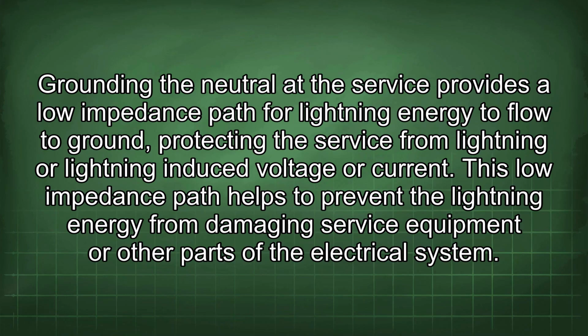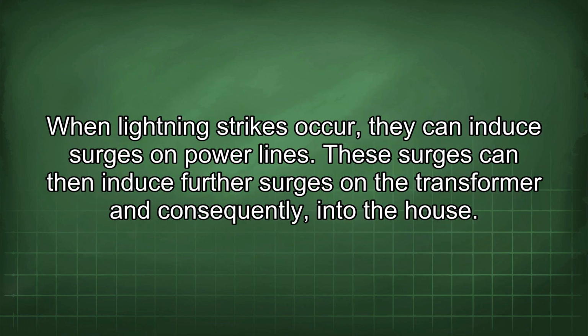Grounding the neutral at the service provides a low impedance path for lightning energy to flow to ground, protecting the service from lightning or lightning-induced voltage or current. This low impedance path helps to prevent the lightning energy from damaging service equipment or other parts of the electrical system. When lightning strikes occur, they can induce surges on power lines.